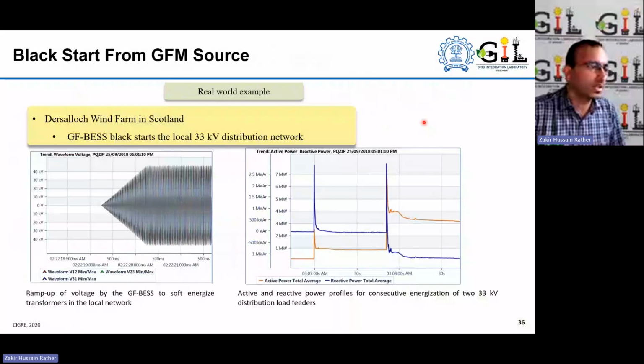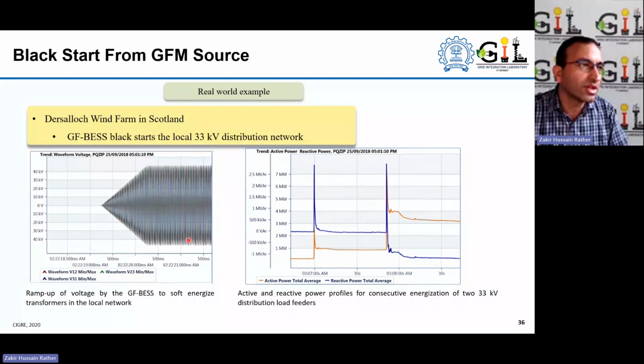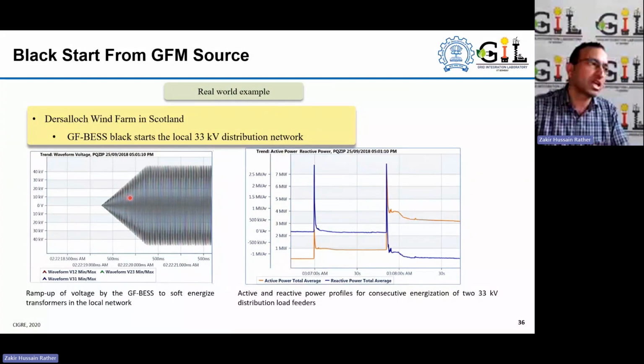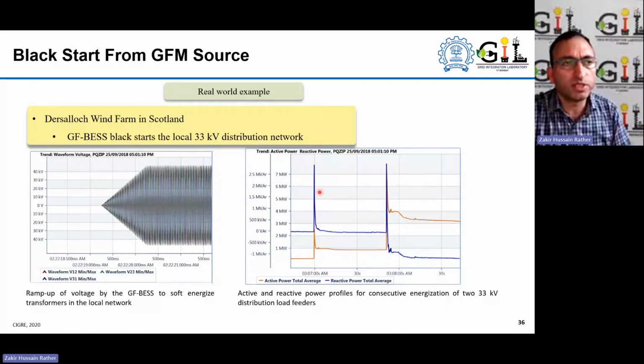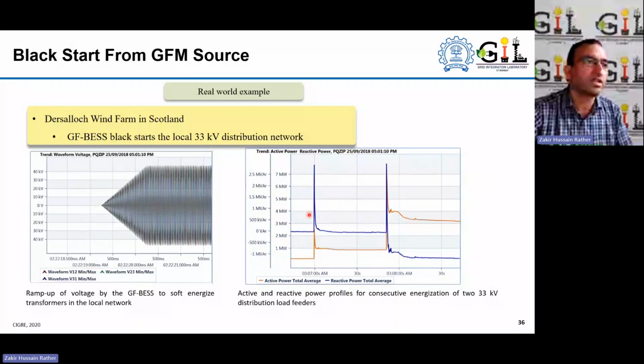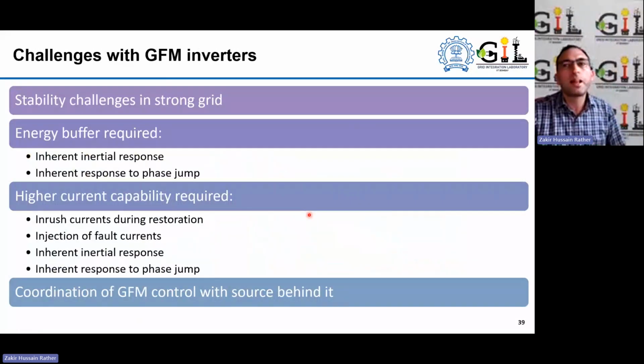This is a field example of the black start capability of this wind power plant, where it is demonstrating the voltage black start of this system and of these feeders. There are feeders that are connected at different points in time, and you can see this inrush current, which is possibly the charging current of the line and maybe transformer inrush current as well, reflected in the spikes here. As a result, it is black starting some of the distribution feeders at the 33 kV level.